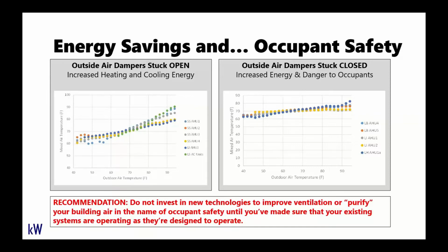And especially now, that is a strong concern with COVID and other general air quality concerns that are front of mind lately. So in correcting both of these issues, we were able to save energy by fixing the ones that are stuck open. We were able to save energy on the high end of the cooling range and the low end of the heating range. And by fixing the ones that were stuck closed, we were able to save energy in this mild range when we would rather have them fully open. And in both cases, we were able to improve the indoor conditions for temperature control as well as ventilation.